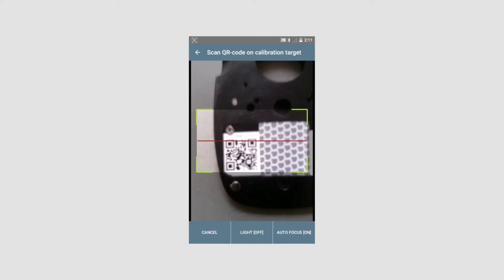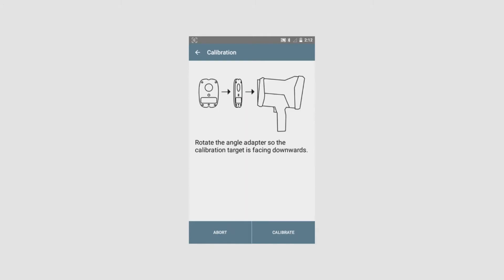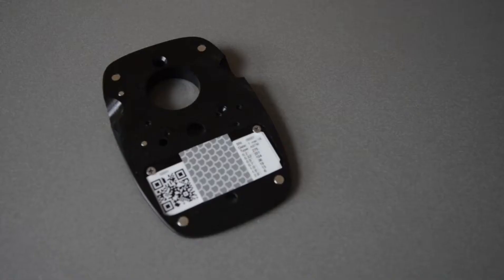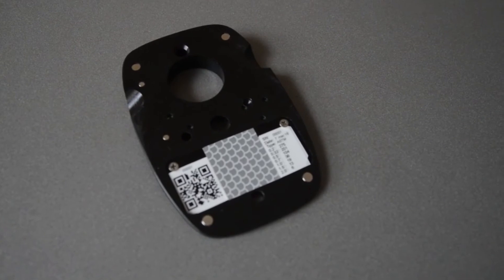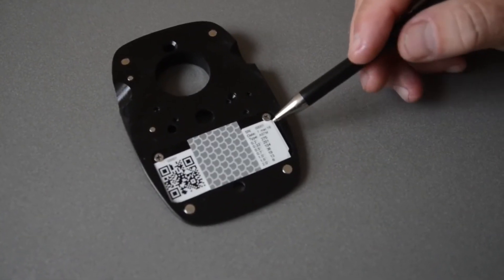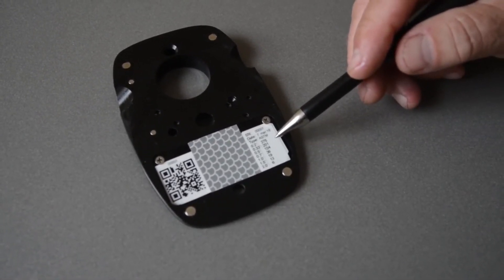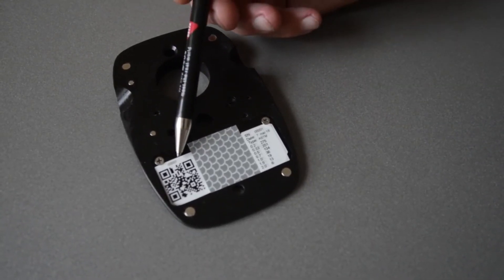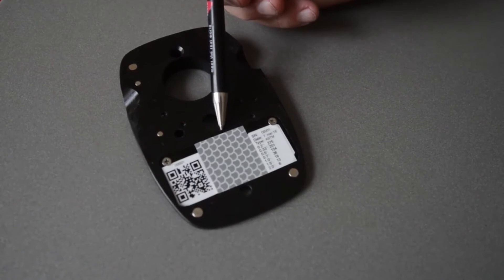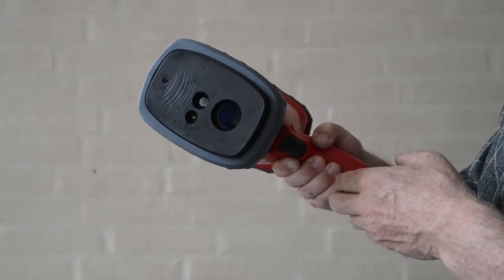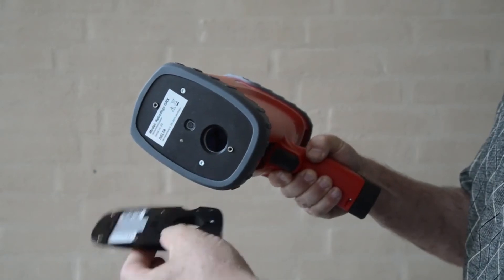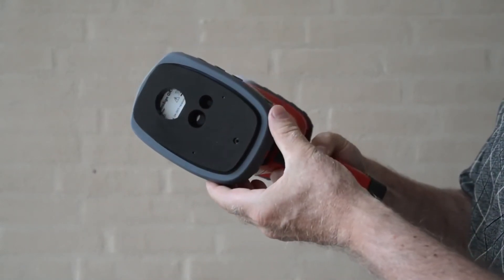The instrument will automatically focus and capture the different values. The next step is to mount the calibration reference on the front of the instrument. Do the calibration and within one or two seconds calibration is done. The relevant tools for doing a calibration is located on the backside of the angle adapter. Here you can locate the values to calibrate up against for the different observation angle, the barcode for the scanning, and the calibration target where the actual calibration is done on. When the calibration figures have been entered into the instrument, the angle adjuster with the calibration target on the back has to be turned around to be able to make the calibration.